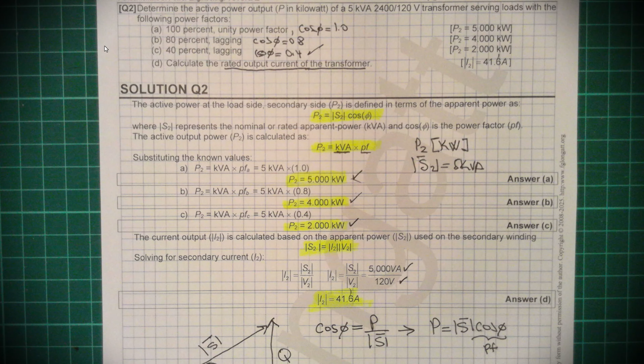This current is 41.6 amps, and that is the rated current at the secondary winding. If we are installing this transformer in any industrial process or machine, we need to consider that the current will never go above this value, because this is the rated current. The rated current is the current the transformer can work with forever without damage, overheating, or negatively affecting the life of the transformer. That's why this number is extremely important.